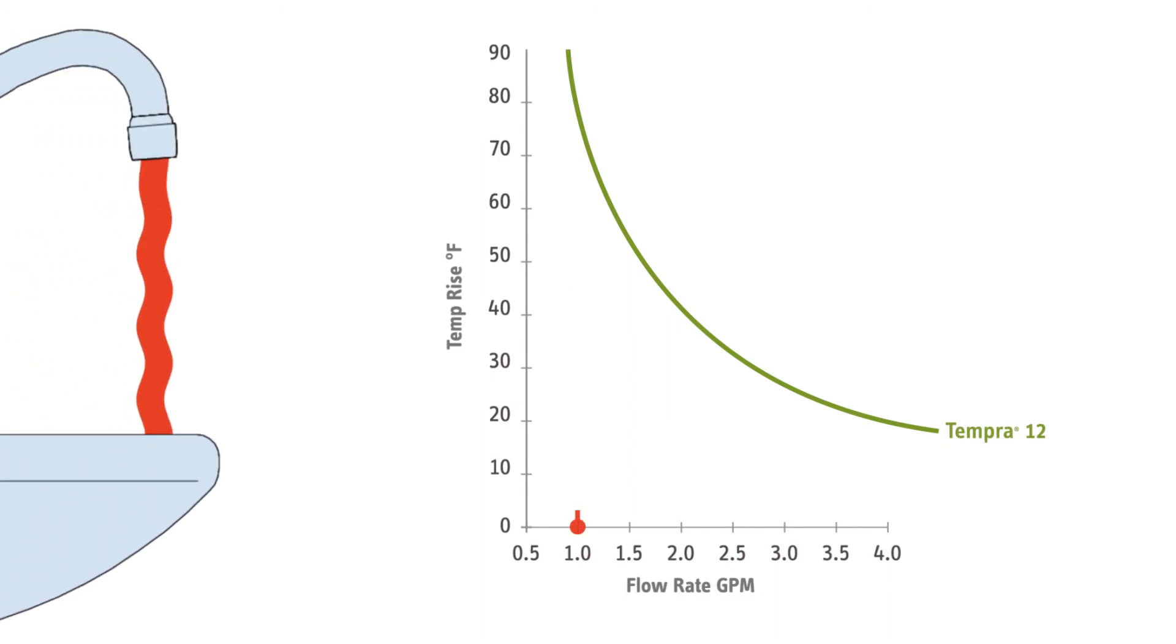For example, imagine a tankless water heater model that can raise the temperature of water almost 80 degrees at a flow rate of one gallon per minute. If the flow rate increases to two gallons per minute, that model will not be able to raise the water temperature that much. Or if the temperature rise needs to be greater than 80 degrees, then the flow rate will be less than one GPM.